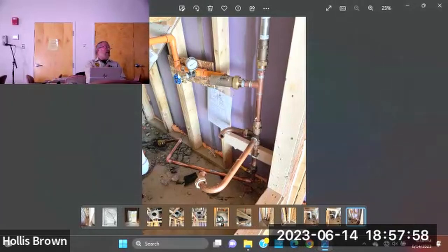The sprinkler pipe that it will eventually be connected to, hopefully it's a wet sprinkler system. There are dry sprinklers in the commercial world, but 90% of residential sprinkler installations are wet, so there's going to be water in that pipe. Why are there two of them? We can get backflow from two different directions. The Watts 7S protects the stagnant water in the sprinkler system from backing up into our drinking water. The simplest explanation: if you flush a toilet, run a dishwasher, and take a shower at the same time, for a moment the water pressure in the house is lower than in the sprinkler system. Without that check valve, some of that crunchy water that's been sitting there for 5 years would get sucked into the drinking water.